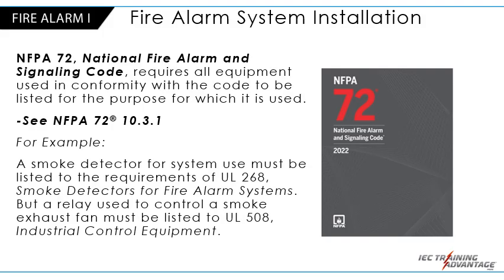For example, a smoke detector for system use must be listed to the requirements of UL 268, smoke detectors for fire alarm systems, but a relay used to control a smoke exhaust fan must be listed to UL 508, industrial control equipment.